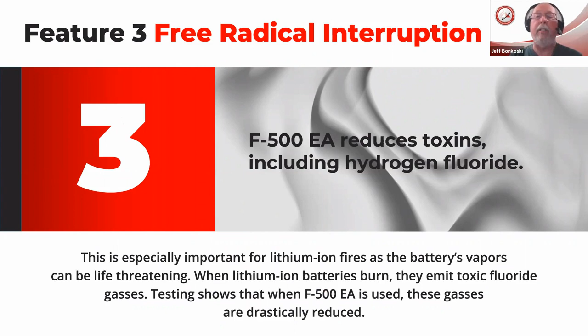But we can show with testing that F500, when used to extinguish these battery fires, reduces those toxins and gases drastically. The effectiveness of F500 on lithium-ion batteries is in all the areas none of the other agents have been able to prove they're effective on. F500 is able to rapidly cool, stopping that thermal propagation and thermal runaway. It reduces the toxins released when these batteries burn, making scenes safer and reducing firefighters' exposures.